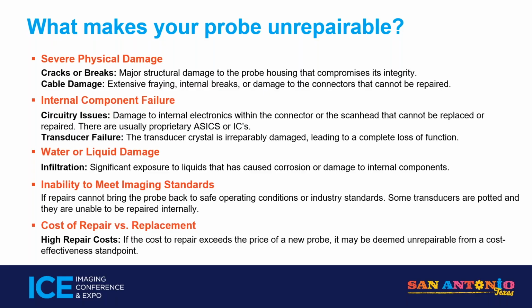So sonographers need to take those out of service, and that's your job when you evaluate them. Get them a loaner - some can't live without it. Get it out of service, get it repaired and evaluated. If it's a cable, they can replace the cable. If it's the array, it's a new probe. But at least your diagnosis will be accurate, and that's what we're really looking for.